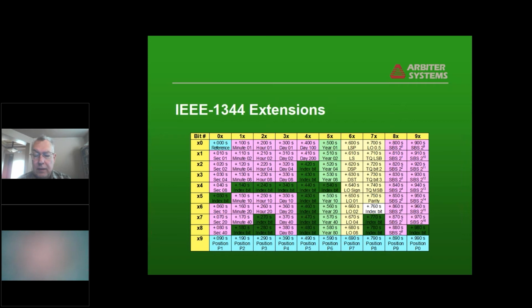This is what they look like. On the left-hand side, it's the basic time information in seconds, minutes, hours, days. And in the column 5X, you see the year information that's been added. Columns 6 and 7 have the extensions that were added by the IEEE 1344 standard, the synchrophasor standard originally: leap second pending, daylight savings time pending, daylight savings time in effect, and so forth down. There's a bunch of other information. TQ there is the time quality, LO is the local offset. All that information has been added.